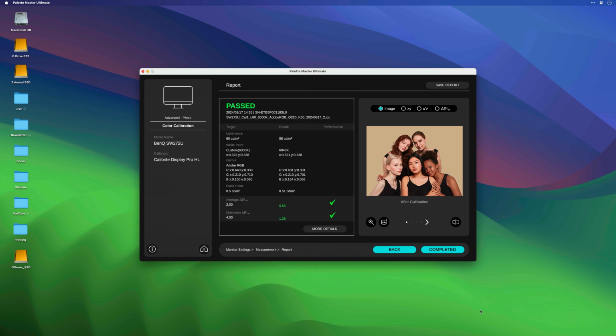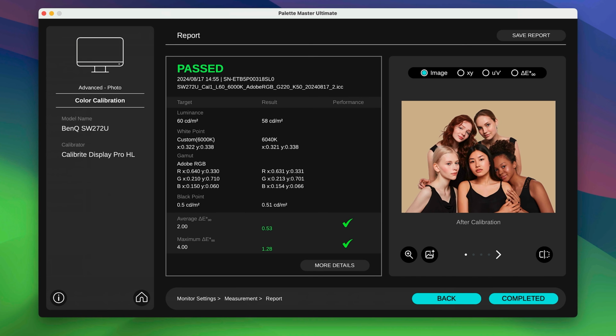So once the calibration process is finished, we can then check to see the results. So I'll click on Check Report. I can see here first of all that the calibration has passed and what my target settings were next to what was achieved in the calibration process. So for example, my target luminance value was 60 candela and it achieved 58. White point target was 6000 and it achieved 6040. Black point target was 0.5 candela and it achieved 0.51 candela. So all of those results are definitely acceptable.